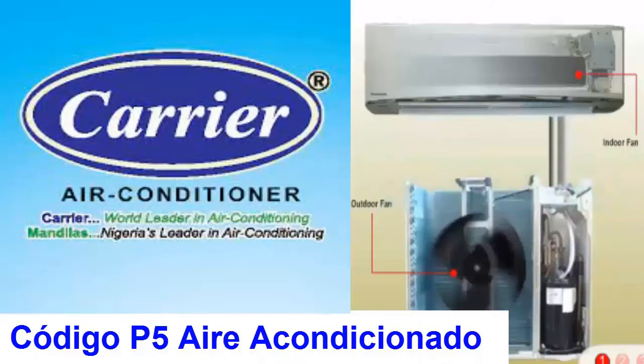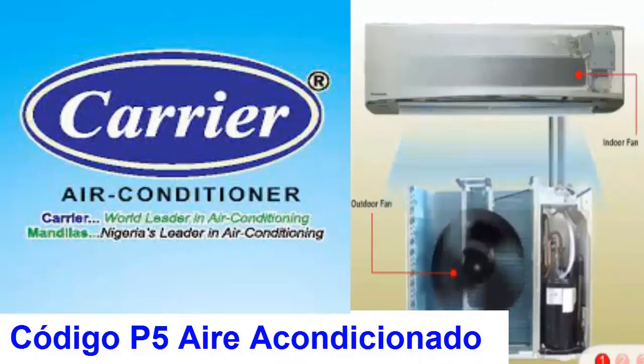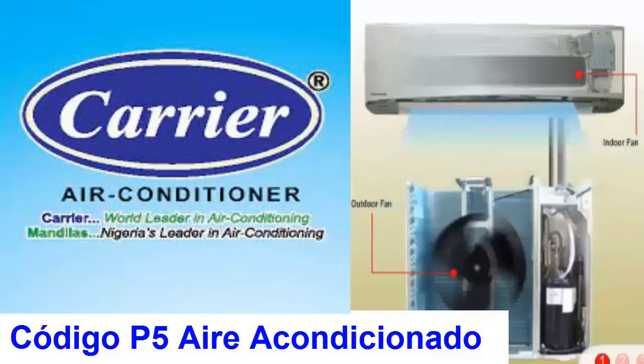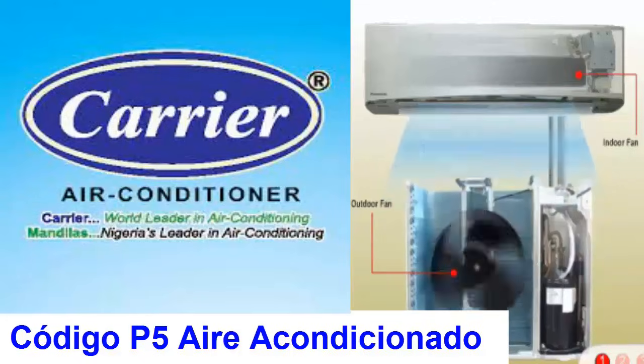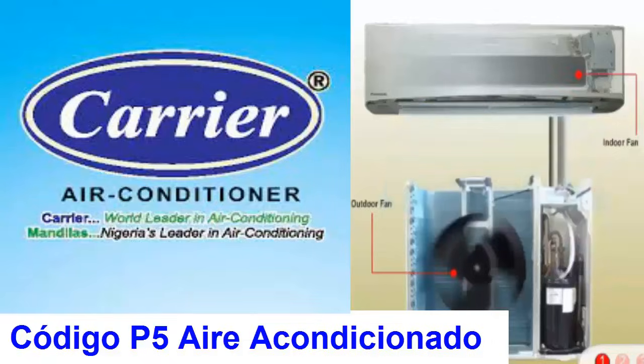8. For Carrier, if the P5 code appears on the indoor unit, it indicates a mode conflict between indoor units or between the external and internal units, which must be corrected by adjusting the settings. If the code appears on the outdoor unit, it indicates protection due to high condenser temperatures, so the heat exchange should be checked and any problems resolved.